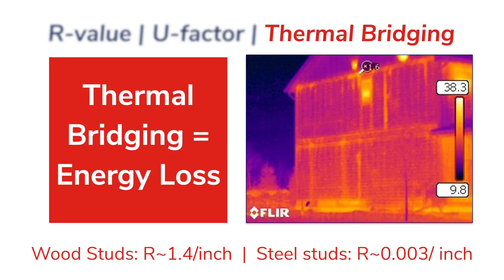Now on to the concept of thermal bridging. Wood and steel framing members that make up a building have low R-values, and steel is a highly conductive material. This is significant because heat always wants to travel along the path of least resistance, and materials with low R-values offer an excellent heat pathway for this. The movement of heat across materials more conductive than their surroundings is called thermal bridging.